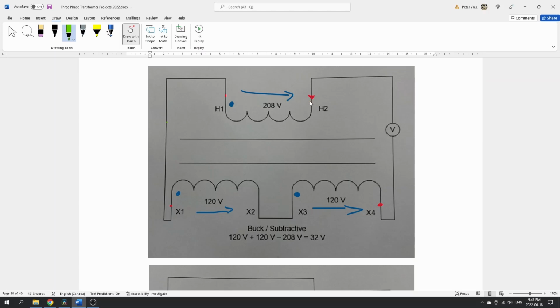So we're going to start here, and we've got 208 volts, but we get negative 208 because we're going against the arrow here. Then we've got a positive 120 plus positive 120. So in this case, we have 240 volts minus the 208, and we're expecting to see a voltage of 32 volts. If we go in the opposite direction from this connection here, we're again going against the arrow, so we're negative 120, now we've got negative 240, and then we get a positive 208. So the difference between the 240 we're seeing down here and the 2.8 up here should result in a voltage of 32 volts.